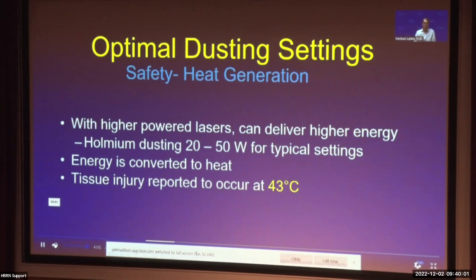With these settings we run into a concern with heat generation, particularly with the holmium laser. We're talking about dusting at 20 to 50 watts for typical settings. At these high powers, a high amount of energy can be delivered, and this energy is largely converted to heat within the kidney. We know tissue injury has been reported to occur at about 43 degrees centigrade. So the question is whether we are potentially creating damage within the kidney during dusting.